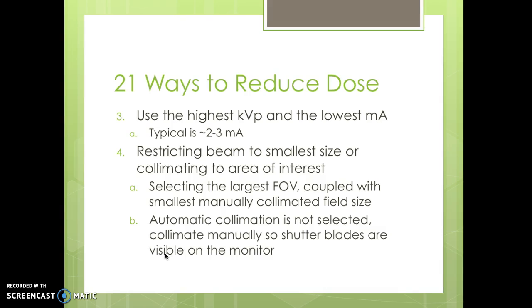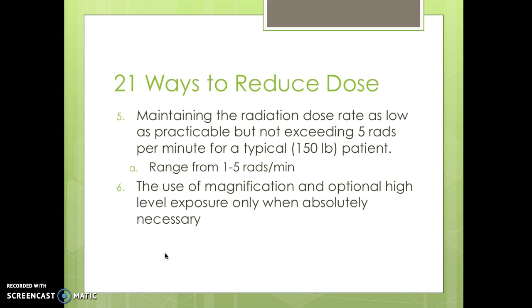Select the largest field of view coupled with the smallest manually collimated field size — automatic collimation is not selected usually. The shutter blades should be visible on the monitor; don't leave it wide open. Maintain the radiation dose rate as low as practical, not exceeding 5 rads per minute for a typical 150-pound patient — the typical range is 1 to 5 rads.